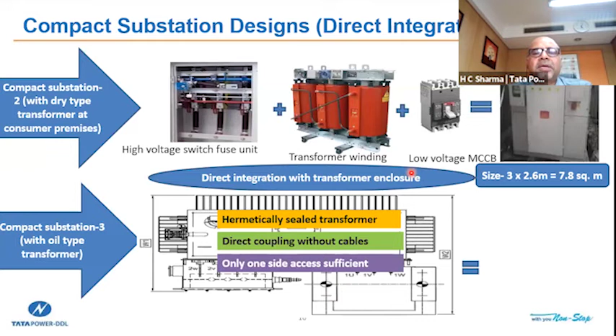Going further, for weather-neutral systems we developed an underground substation. We previously had underground substations too, but water seepage into the system could become dangerous for the public and cause leakage. Now, with a system designed indigenously using indigenous equipment, we have made it a submersible substation—even if the transformer is submerged in water, it will keep supplying power.